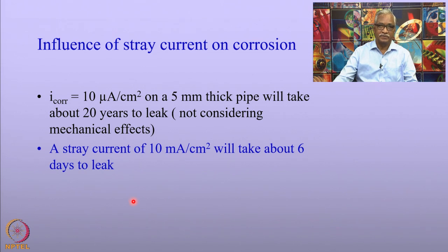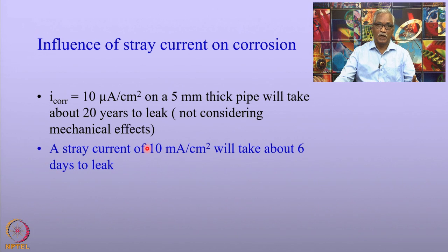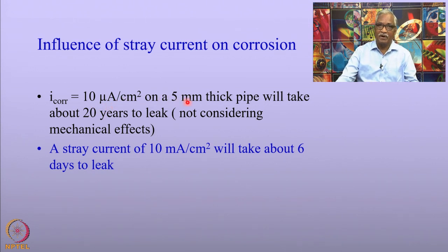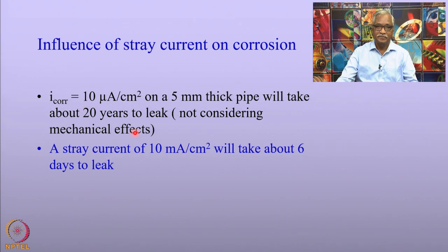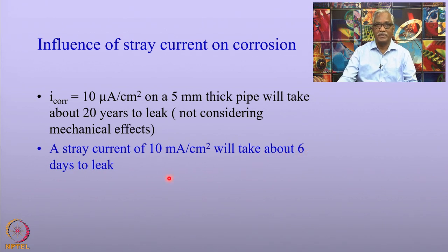Why should we be worried about stray current corrosion? Normally, pipelines will have a corrosion current density of the order of 10 microampere per centimeter square. If the structure is 5 millimeter thick, it will last 20 years before a leak commences, assuming mechanical effects are not in play. On the other hand, for a stray current corrosion of the order of 10 milliampere per centimeter square, it will take just about 6 days to leak. That is the severity of stray current corrosion we should be worried about.